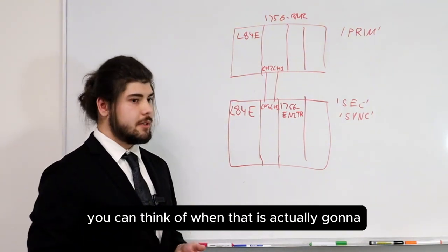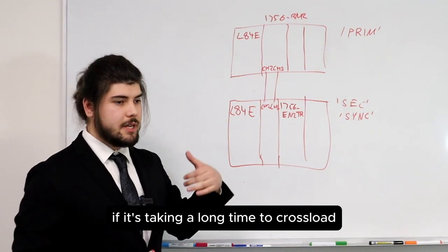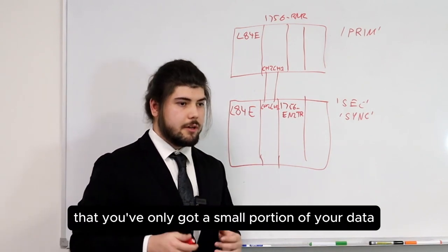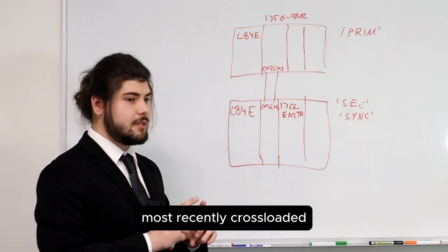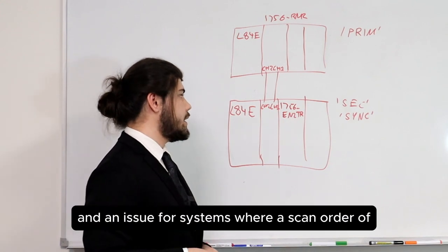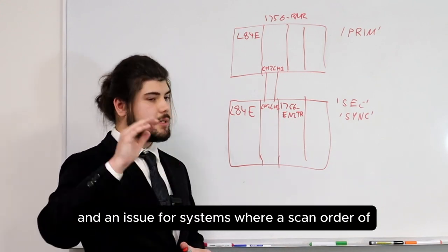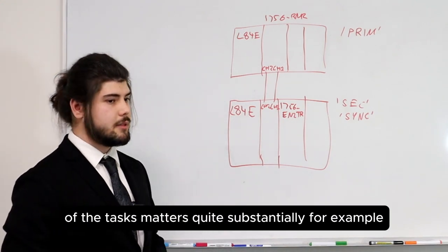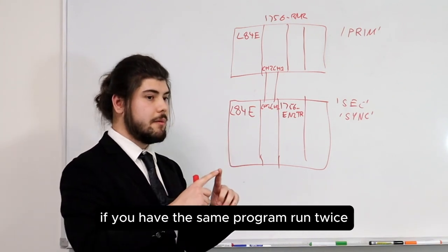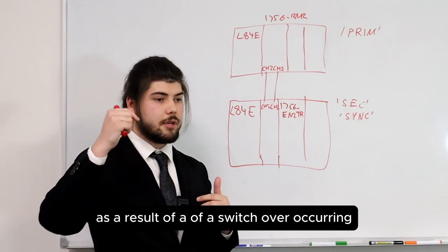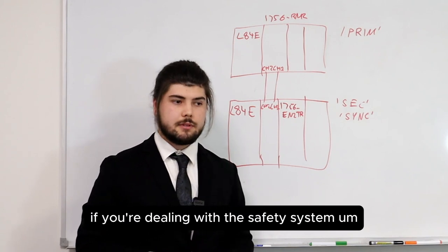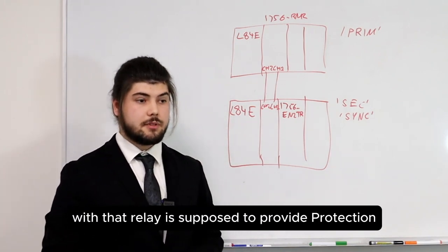The program's memory organization matters when approaching a switchover event. If it's taking a long time to cross-load and a switchover event occurs in the middle, you've only got a small portion of your data most recently cross-loaded. That can be a big issue for systems where timing or scan order of tasks matters substantially. For example, you could be closing and opening a relay if the same program runs twice as a result of a switchover — which would be a massive issue if you're dealing with a safety system where that relay is supposed to provide protection.